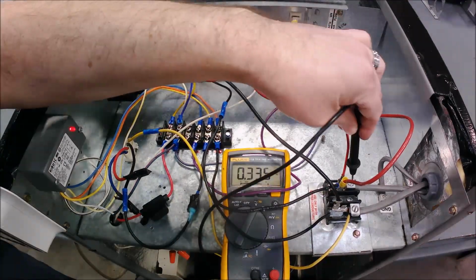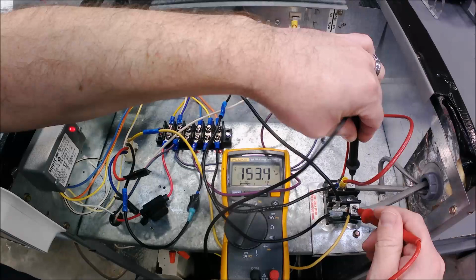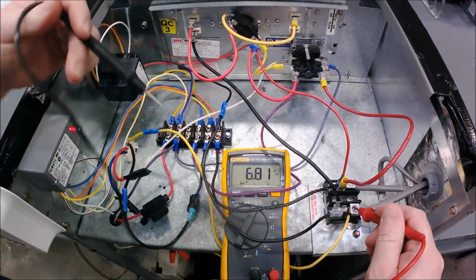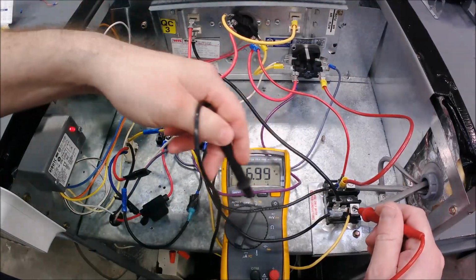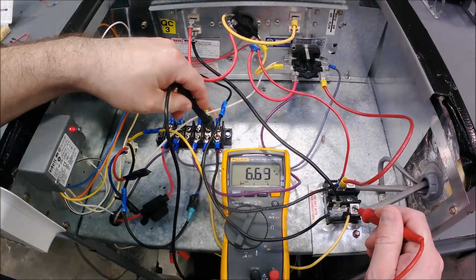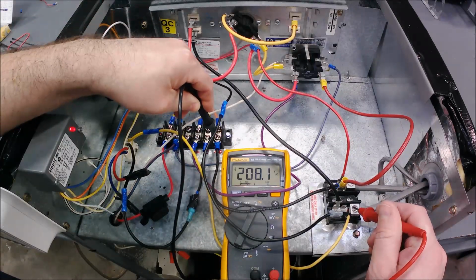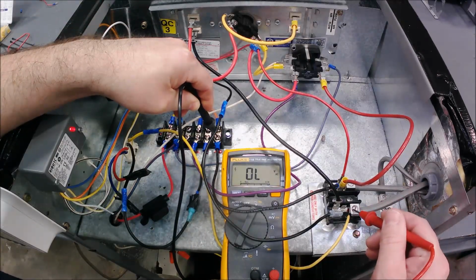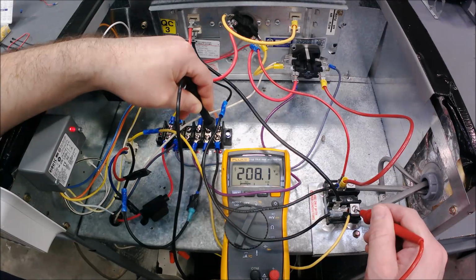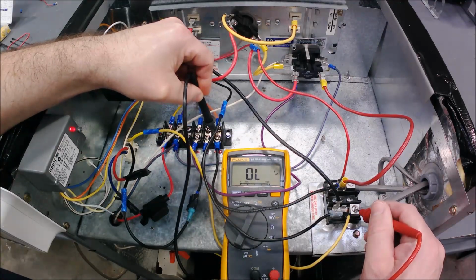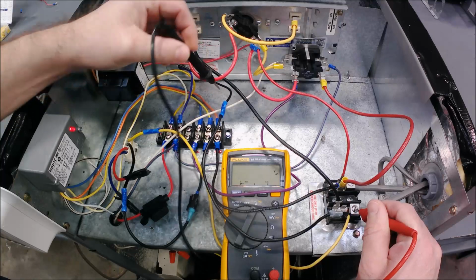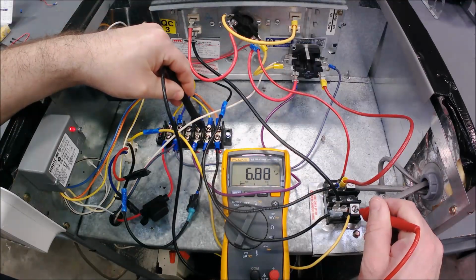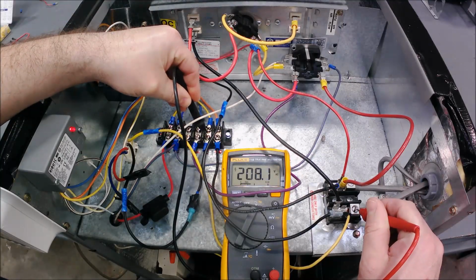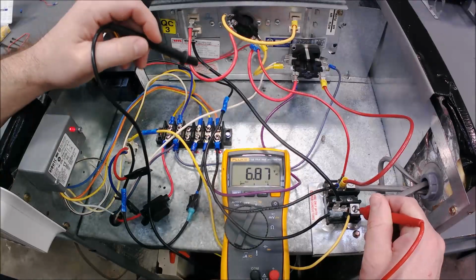Alright, so this is L1 and this is L2. I've only got the fan on, so if I was following, I would follow this going into the normally open. So I've got my L2 over here on this bottom terminal screw of the terminal block. That's power going in. If the switch is closed, then it'll come out here on the common. So I know that my fan should be running, and of course it is.